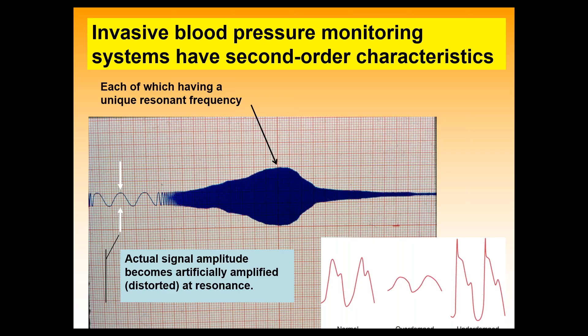And the significance of that we'll see in a bit. Here is the input pressure signal going into the pressure transducer. So you've got a constant amplitude signal here. This could be 120/80, say, equivalent blood pressure. All I did here was increase the frequency, didn't adjust the amplitude at all, just the frequency of the signal. As the frequency of the signal approached the system's resonance, you can see how artificially big it got. The significance of that clinically is that it's going to distort the real blood pressure. It's going to artificially elevate systolic and reduce diastolic pressure. It's going to distort the very signal that you're trying to measure at this resonance.